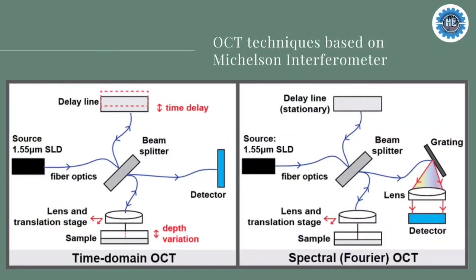Here is the image showing the OCT techniques based on the Michelson interferometer. In Time Domain OCT, it uses time delay based on the encoding of the location of each reflection in the time information relating to the position of a moving reference arm mirror. In Spectral Domain detection technology, it is based on the use of Fourier transformation of the frequencies of reflected light, acquiring all information in a single axial scan through the tissue and detecting all light echoes from different delays, thereby improving imaging speed.